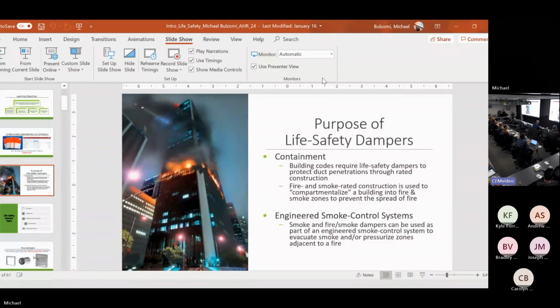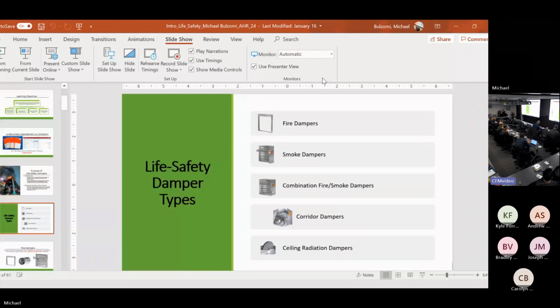Why do we need them? For containment, we want to contain fire. We don't want it to spread. We want to compartmentalize buildings, right? So we're going to have rated walls, rated barriers to make sure that if there is an event, smoke zones, different things, that fire doesn't leave the point of origin and do any more damage and endanger lives, as well as engineered smoke control systems, code required for certain buildings and certain occupancies.